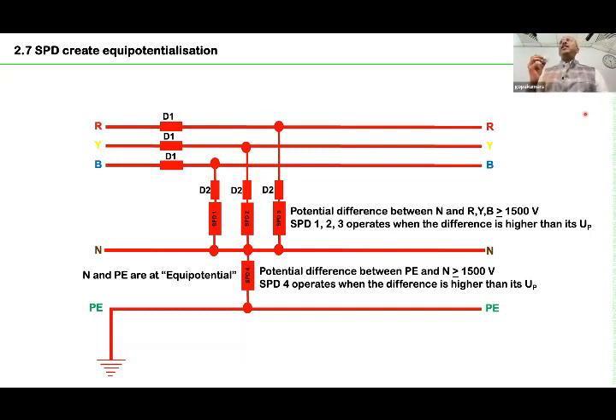SPD is a very critical subject. Even at the IEC level, there are still a lot of discussions and research going on to develop or increase the safety of SPDs. The challenge is always that the SPD fails, but the backup protection doesn't work. There is an MCB or there is an HRC fuse. Before the HRC fuse blows, the SPD will burn. In a lot of cases, we can say. So this is what the SPD does. It creates an equipotential bonding. Immediately after the transient, it returns to the original position.